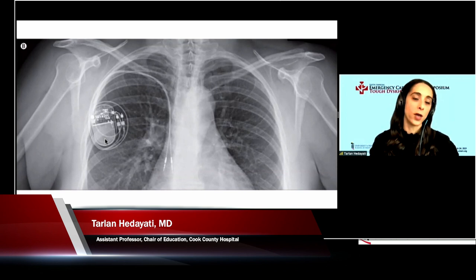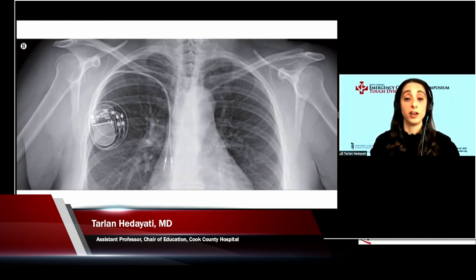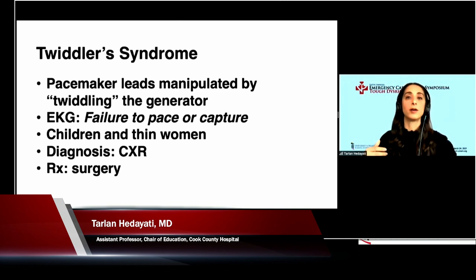This is a great example of twiddler syndrome. This is where the pacemaker leads are manipulated by the patient. They start twiddling the generator or twisting it, and that can cause failure to pace or failure to capture. Typically in kids or in thin elderly women who don't have a lot of subcutaneous fat to anchor that device.